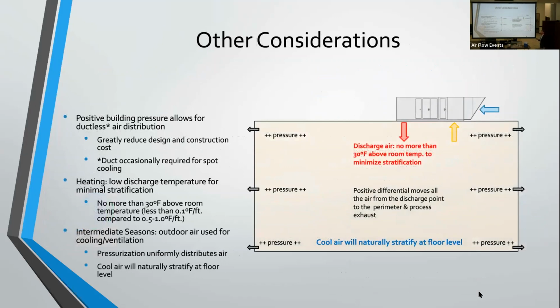A couple other considerations to make. So positive pressure, we've been talking about a little bit. Pressurizing that space, this is a big one, as you're blowing that balloon up and pushing that air in all directions, it actually allows for a ductless design, because you don't really need that supply air ductwork to distribute the air like you would in other situations, because you're pushing that air outward throughout the entire space. This reduces your design and construction costs.